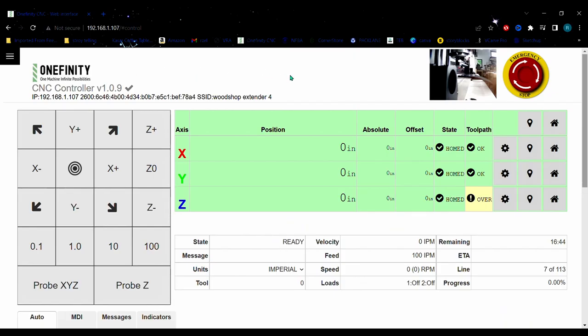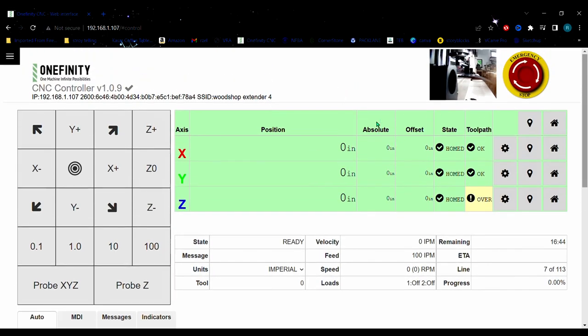Here we are in the software, and I just zeroed and restarted the machine, so everything is at zero. We want all the offsets to be at zero before you start. They must be at zero, okay? It's okay if this says over, nothing matters until you start setting X, Y, and Z.